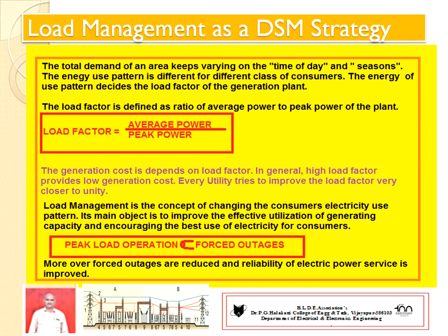One more important fact we have to think about: at peak load operation, that is at the maximum load operation of the plant, every electrical machine, transformer and switchgear is working at its maximum capacity. That is also not desirable. If they operate continuously like this, it will reduce the life of the equipment and there is a chance of shutdown. Once there is a shutdown, it needs operation and maintenance charges, and it also affects the quality of the electrical supply. So for better quality of supply, we need to operate at less than peak load conditions. This is what DSM techniques inform us.